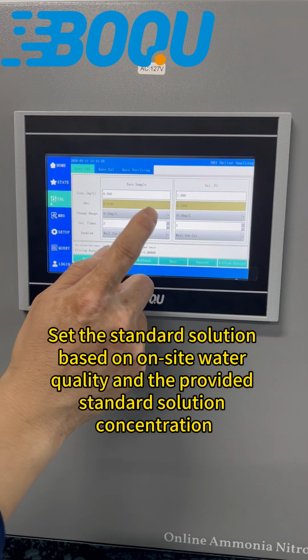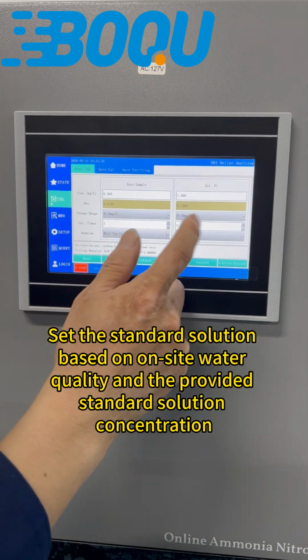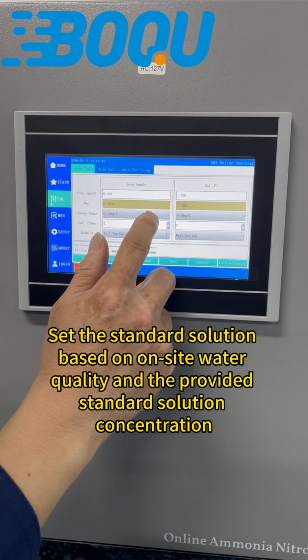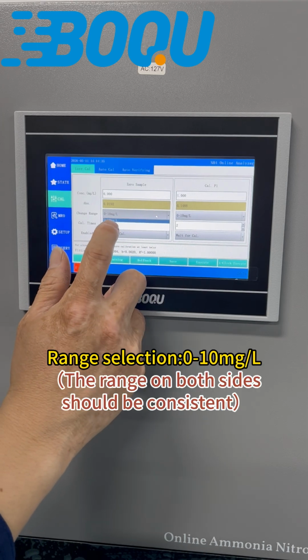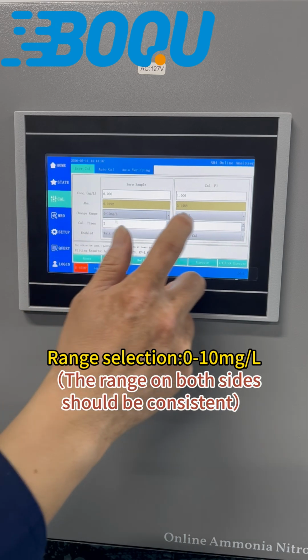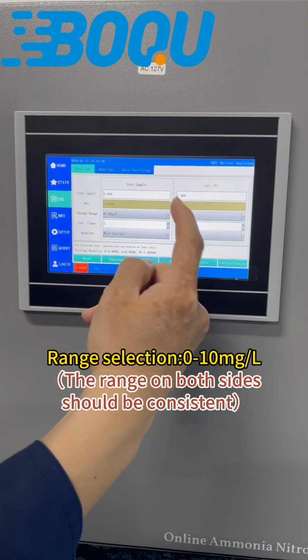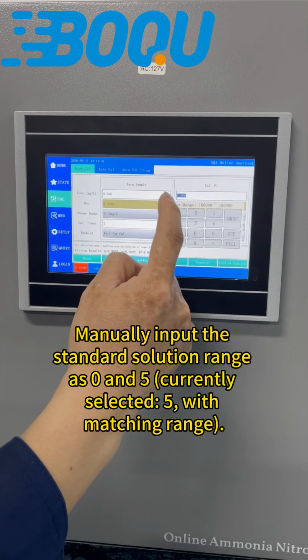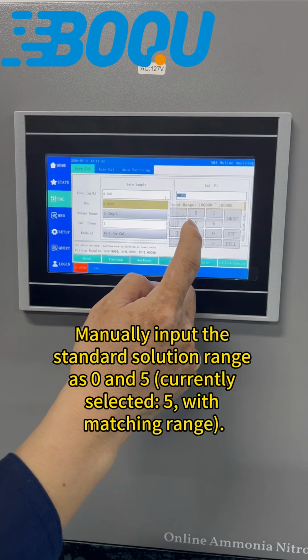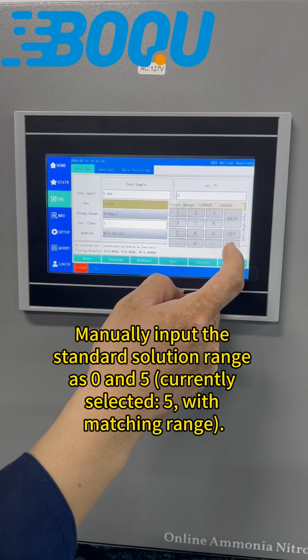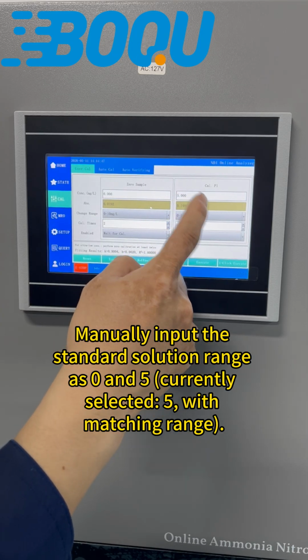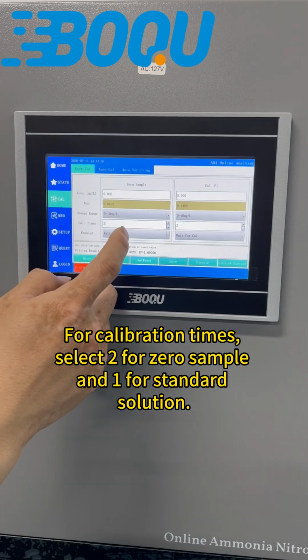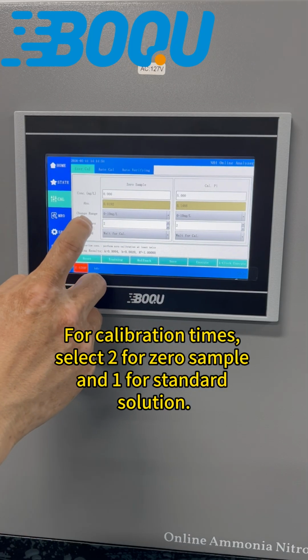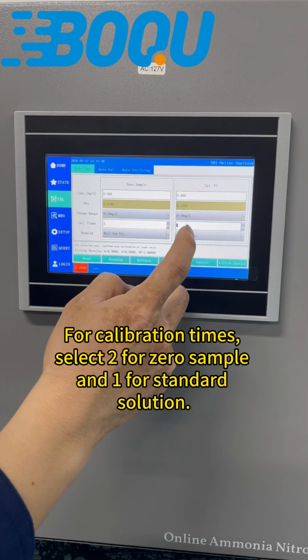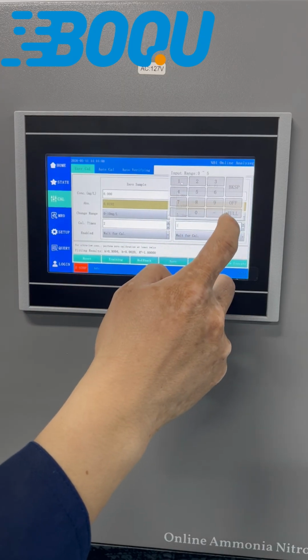Set the standard solution based on on-site water quality and the provided standard solution concentration. Range selection 0 to 10 milligrams per liter. Manually input the standard solution range as 0 and 5, currently selected 5 with matching range. For calibration times, select 2 for zero sample and 1 for standard solution.